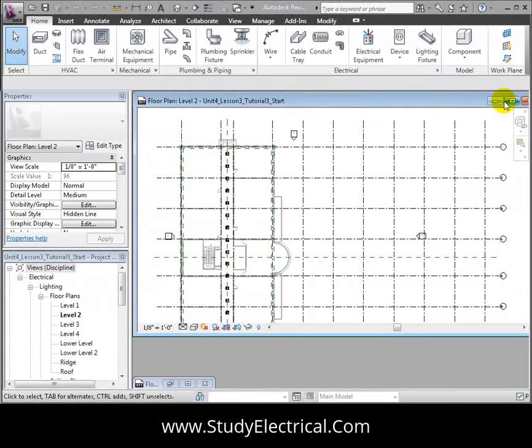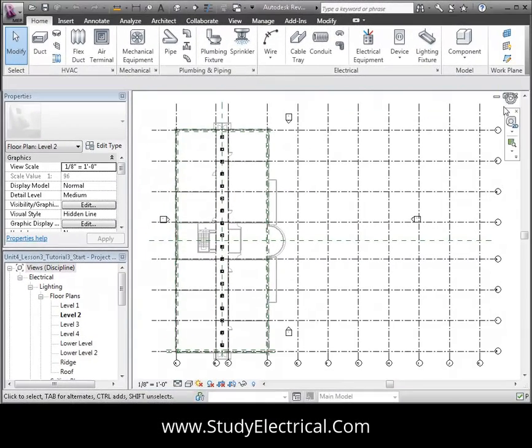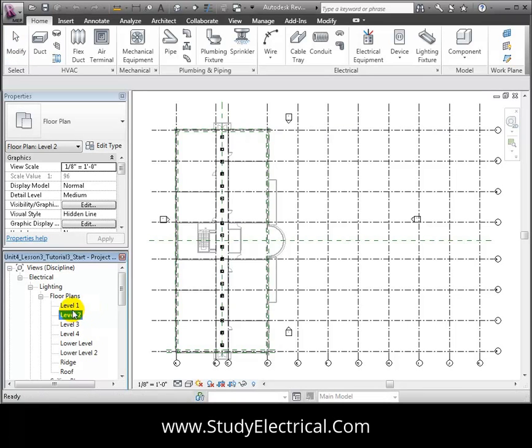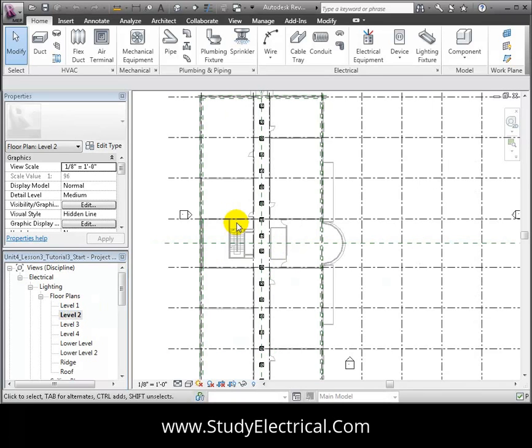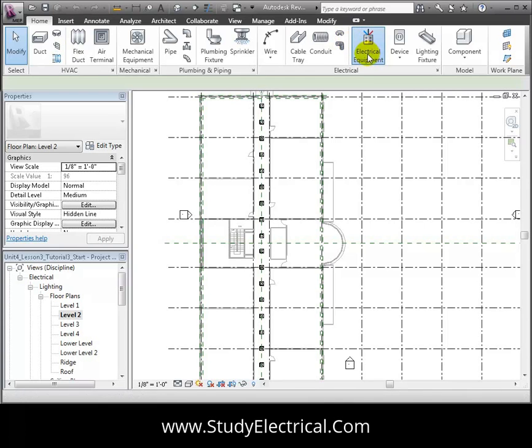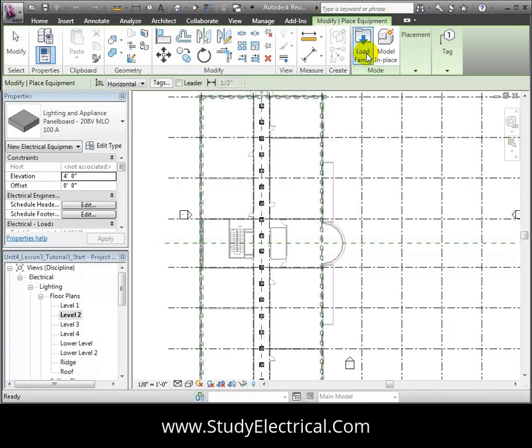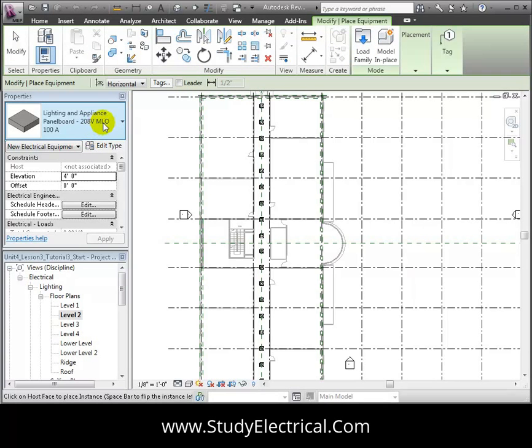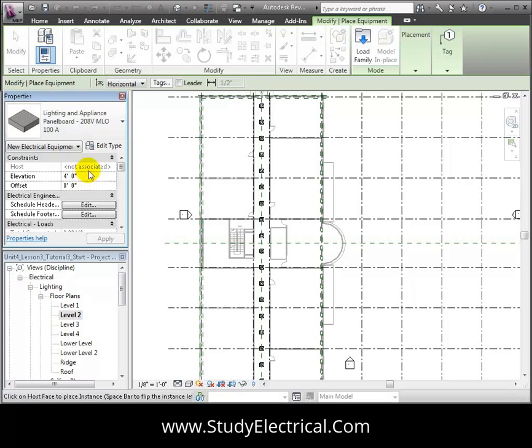We'll open the Level 2 floor plan in the lighting section of the browser. Then open the electrical equipment tool in the Home tab. We'll use the selected electrical panel board type and use the Place on Vertical Face option to place this panel on a wall in the utility room near the stairwell.